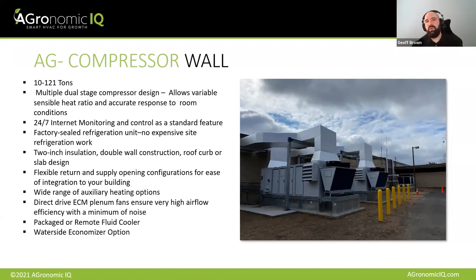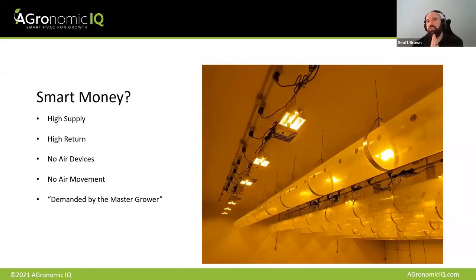But here's an example of a grower that ultimately just didn't choose the right partner to build their building. What we've got here is the top of a grow room. This is a flower room, and this grower has elected to use disposable ductwork with the intent of throwing it out between every flower cycle. They've got typical double end discharge at the top of their room. They've got high supply and high return, or sorry, these return grills here are in the ceiling, and they've got their supply up high. Obviously that ductwork isn't going to be getting air anywhere useful. They've got no air devices in the room to mix the room in any way.